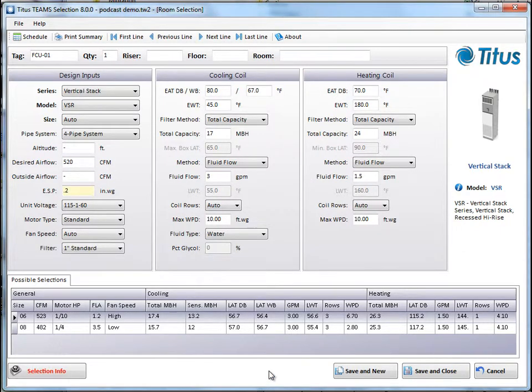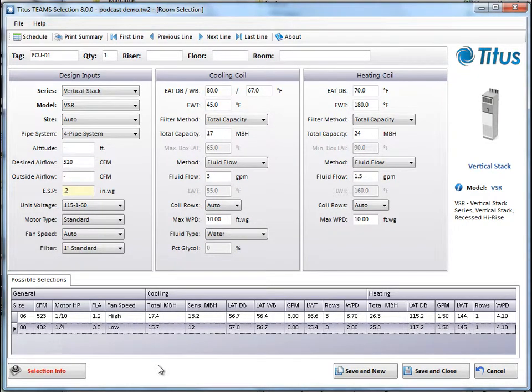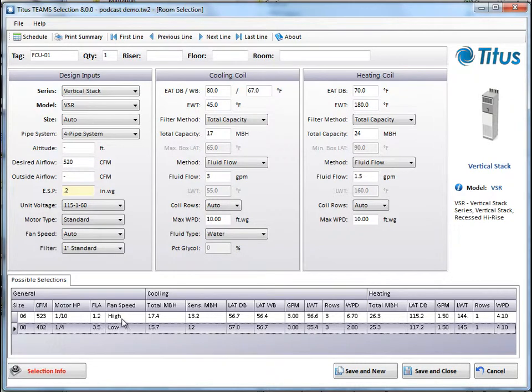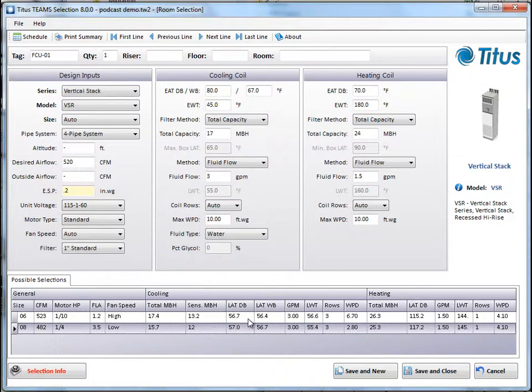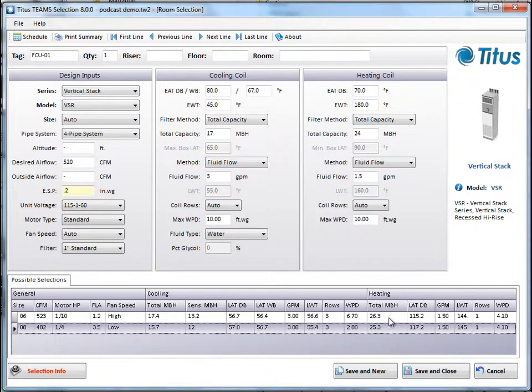And now it's made a selection for us. It says that a size 6 and a size 8 unit will meet our requirements. And if you look at the data, you can see the horsepower, the FLA, it's on the high fan speed. There's our MBH, our sensible MBH, leaving air temperature, dry bulb and wet bulb, 3 GPM, which is what we said we had, our leaving water temperature, three rows, our water pressure drop of 6.7 feet.